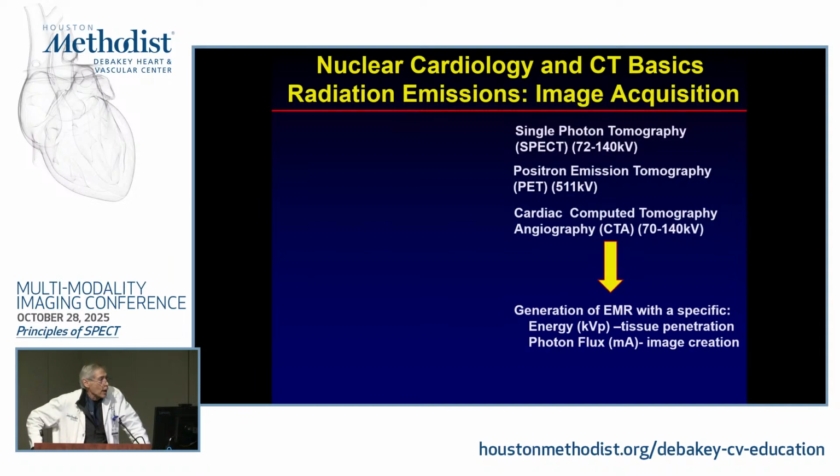Right? So I always think about it in this way. keV is like the train, and the mA, milliamperes, or photon flux is really like the cars behind it. You're carrying all this stuff. So you're really delivering all of this stuff, these photons and these milliamperes via the kV, which is the train locomotive, and that's how we make images.